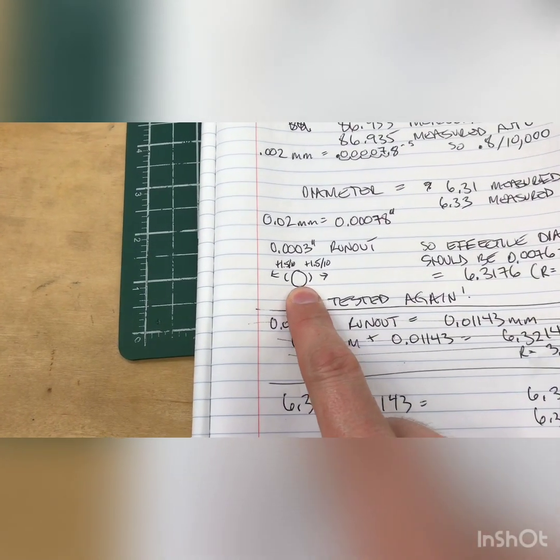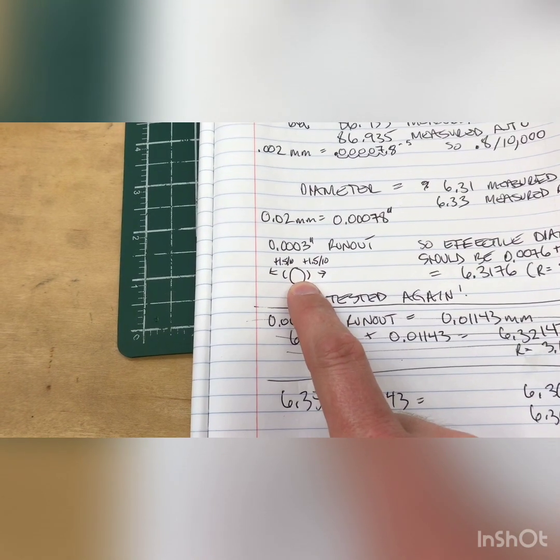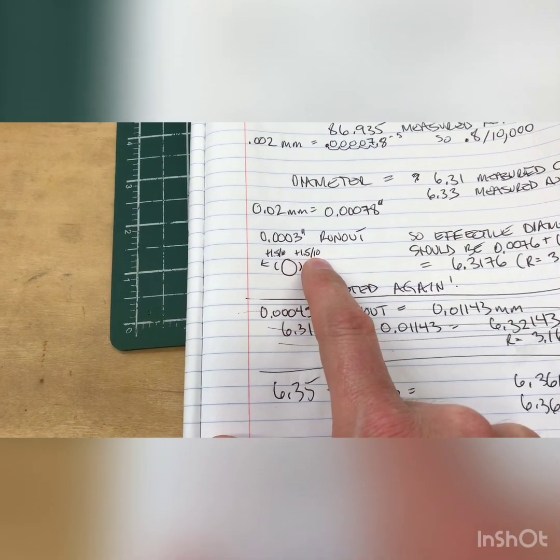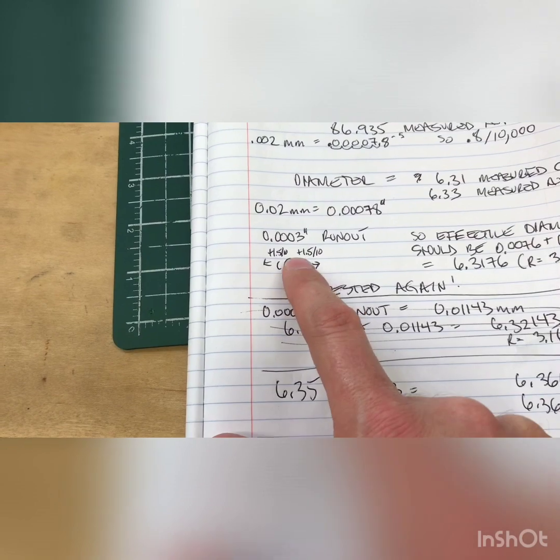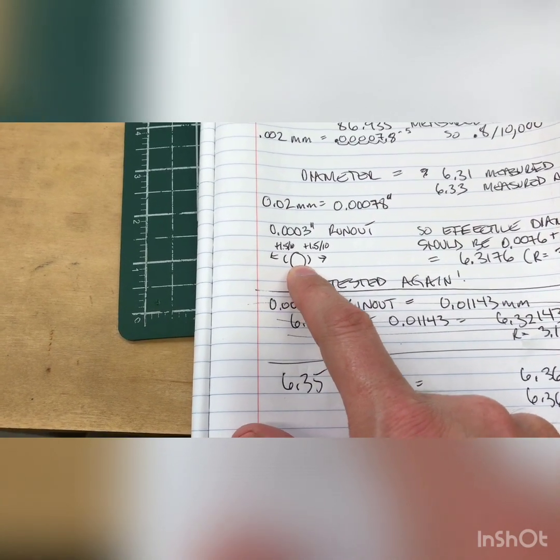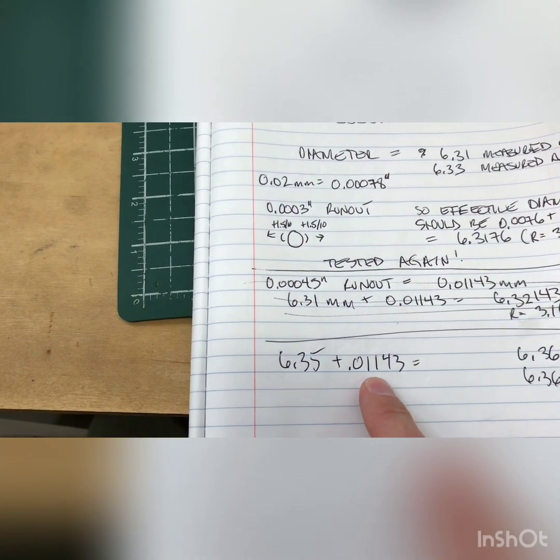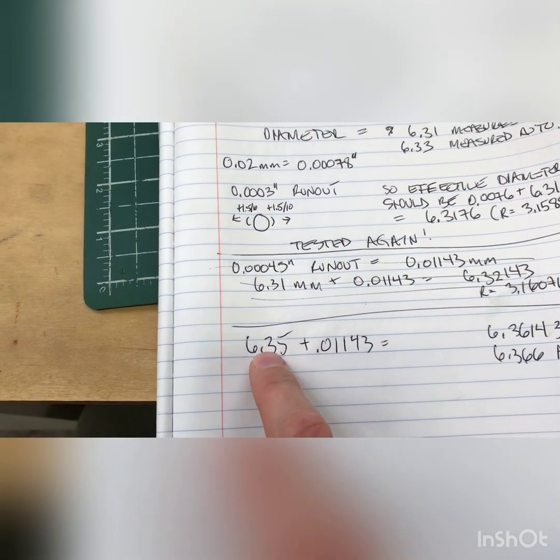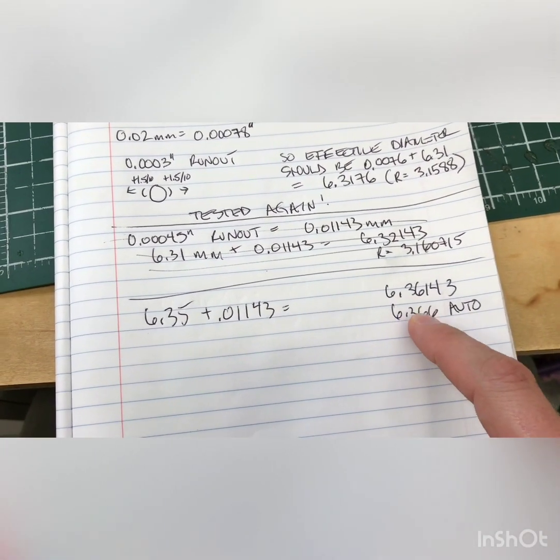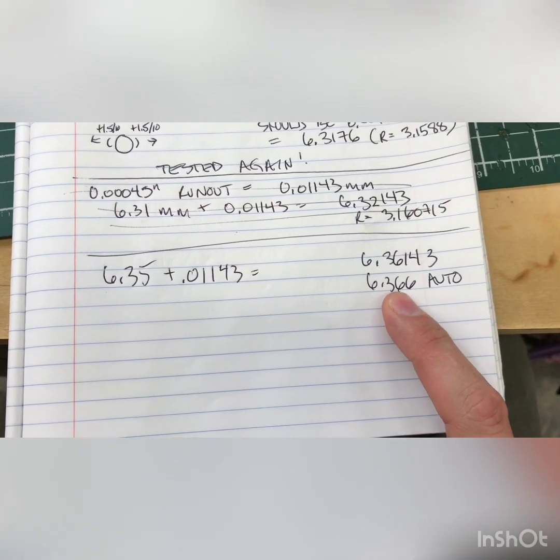We went through the runout together. So that runout, if you think about it, if the diameter is 6.35 and it's running 3/10 runout, that's 1.5 larger at every revolution on this side and on that side. So you effectively actually get an effective diameter that is the amount of the runout, I believe. And if that's true, I can add 0.01143 to the diameter I measured on the bench because of the runout. And when I measure the tool now on the probe, I redid the calibration using 6.35.